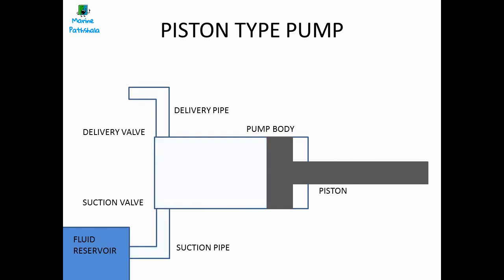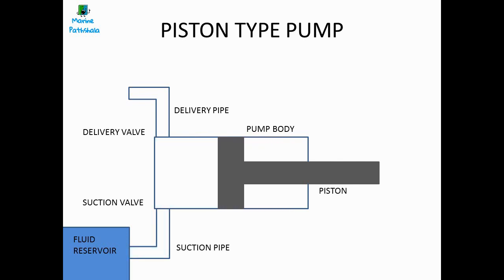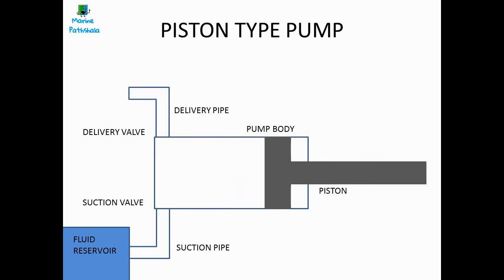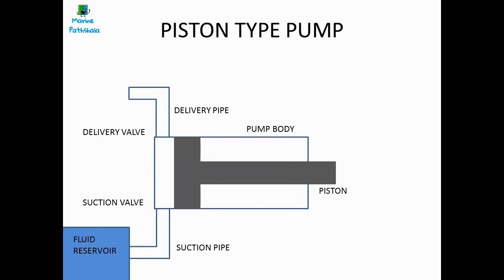When the piston moves forward, the suction valve closes and the piston pressurizes the fluid inside the pump, the delivery valve opens, and the fluid is discharged. This happens continuously and fluid is transferred from one place to another. Since the fluid is sucked into the pump due to the vacuum created and does not require any external means, these pumps are self-priming pumps.